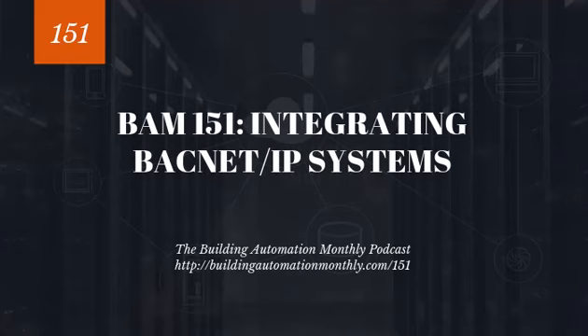Now, at this point, we are going to make sure that our BBMDs and BDTs are configured. We're going to make sure our network IDs, our subnets, and ports are set up according to what they need to be set up to. And then we move to our device. And it's at this point that we are going to focus in on our device ID. We're going to understand the protocol implementation conformance sheet, or PIC sheet, and its capabilities. And we're going to make sure we're not trying to do something with that device that the device is not capable of.